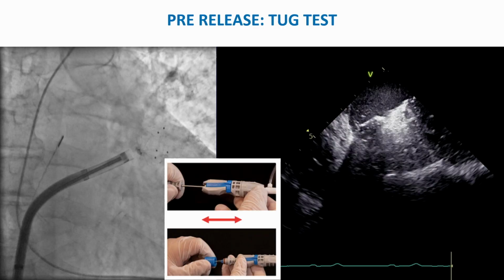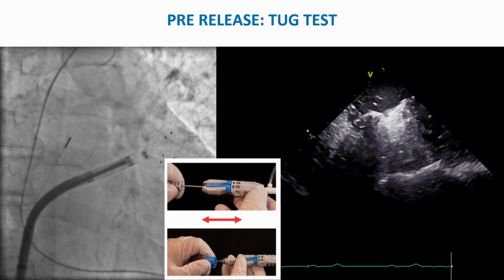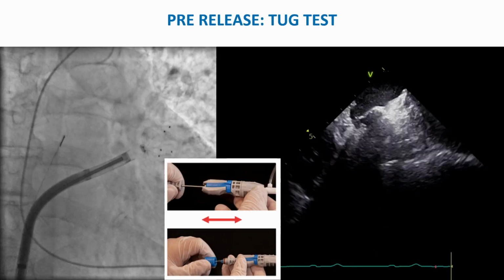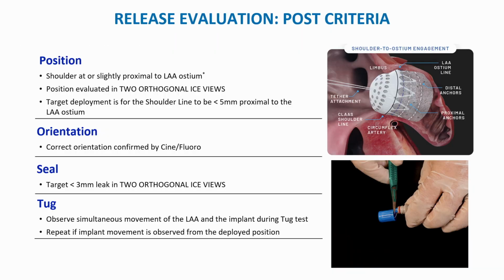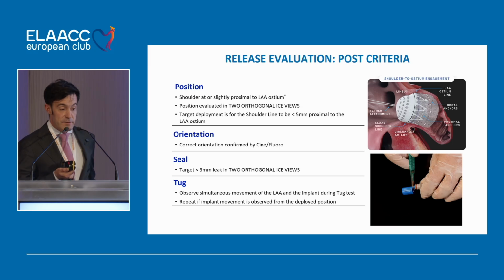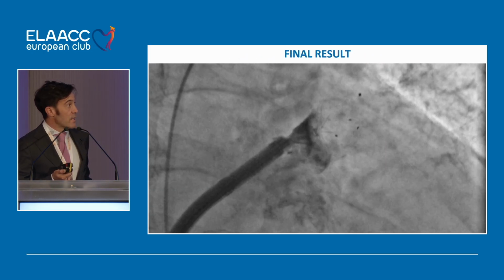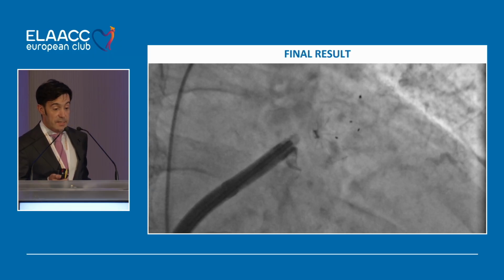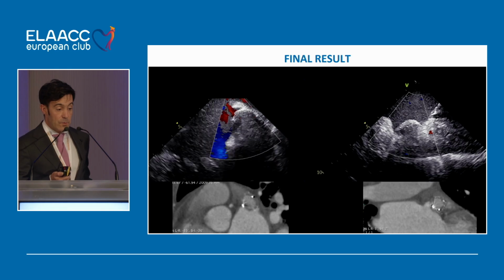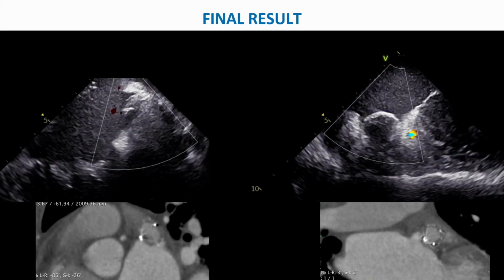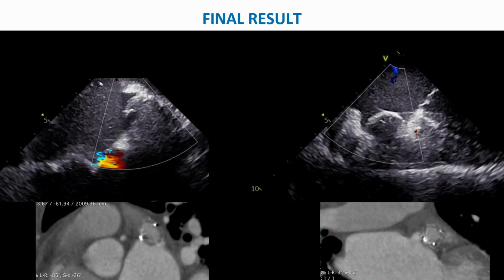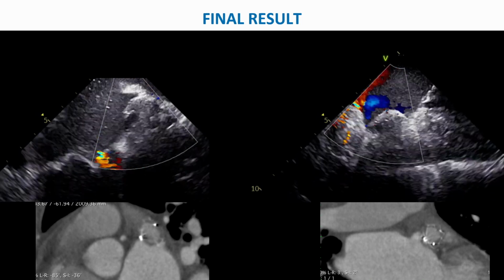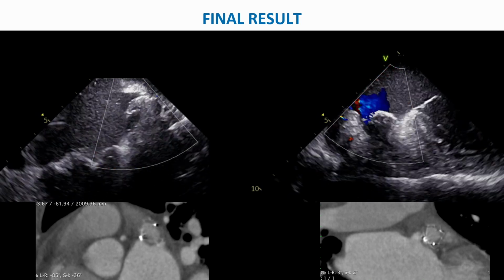Then in this condition of released tension, you perform the tug test, so you check for the stability of the device, and you evaluate all the criteria that in this case are with this acronym: P for position, O for orientation, S for sealing, and T for tug. And then you release the device with this magnified final result, and with this result at echocardiography when you have completely released the device from the tether that kept it attached to the delivery, to the implant system.